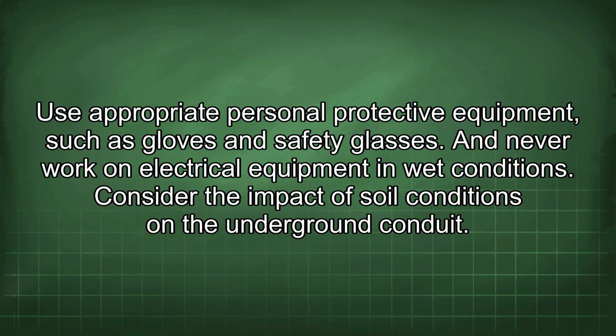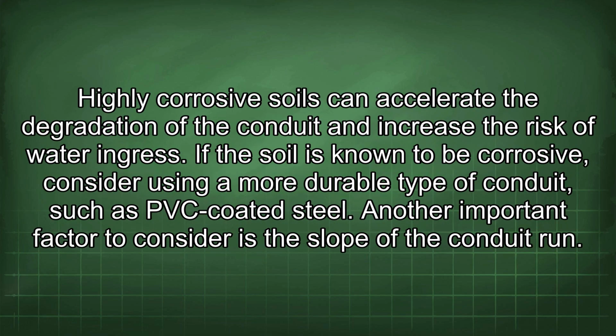Consider the impact of soil conditions on the underground conduit. Highly corrosive soils can accelerate the degradation of the conduit and increase the risk of water ingress. If the soil is known to be corrosive, consider using a more durable type of conduit, such as PVC-coated steel.